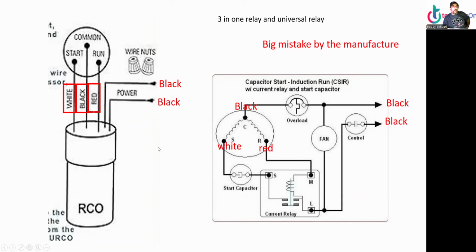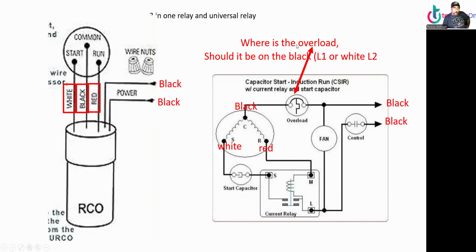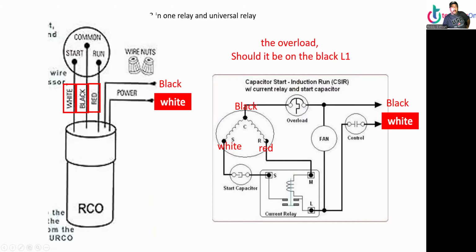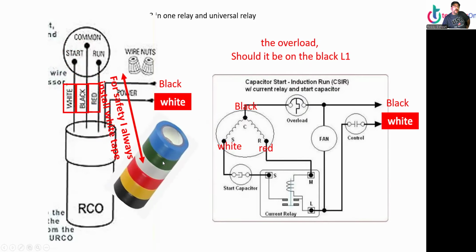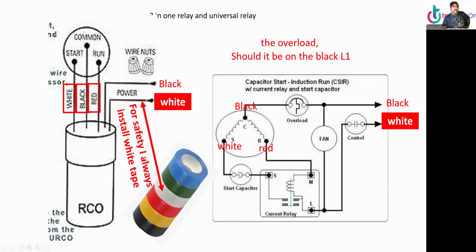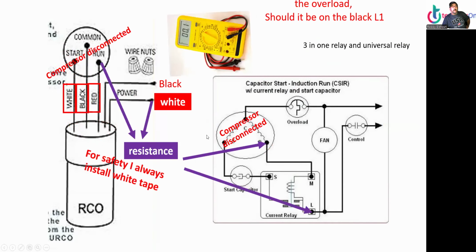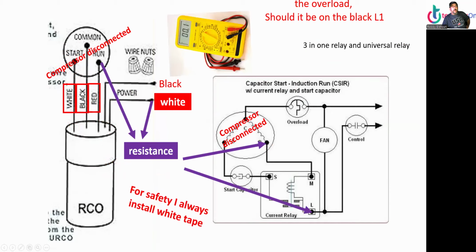Which one is neutral? Alrighty. Where should the overload be, in the black L1 or the white L2? The overload should be in the black. So there we go. This should be white. I can't believe people make that mistake all the time. So before I install these babies, I get my own meter. I ohm them out. For safety, I always put white tape on the black wire to know this is the white. I ohm out the resistance. And between the white, one of the blacks, and the run should have resistance, right? Because that's the run winding.